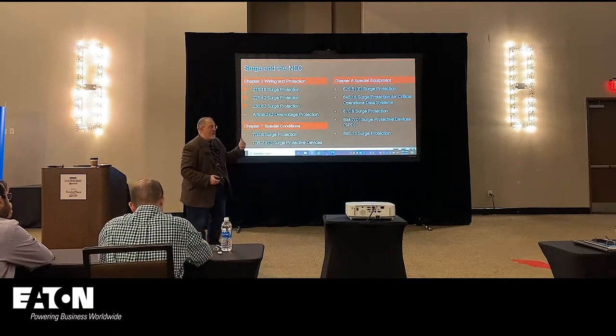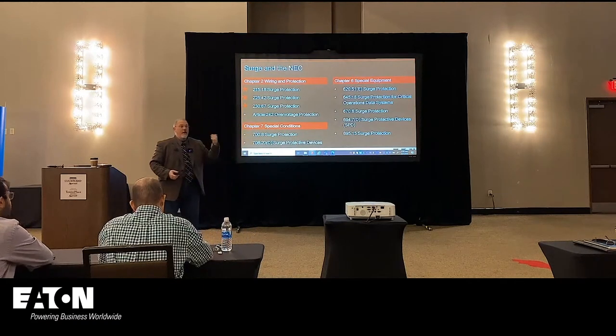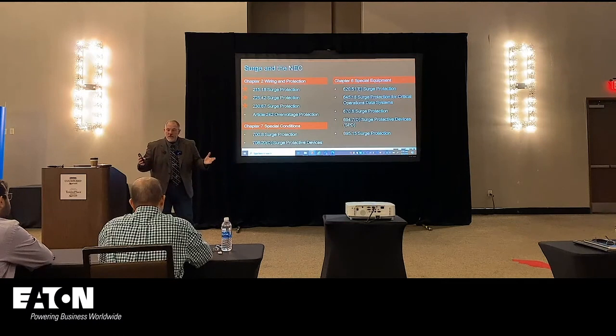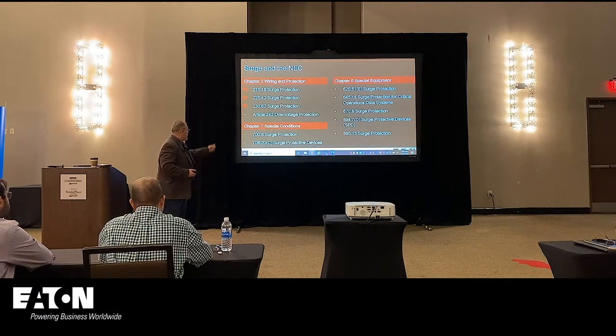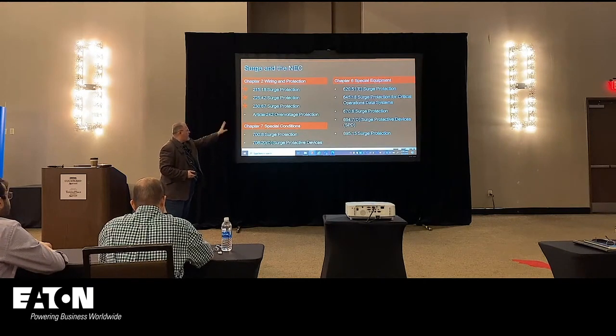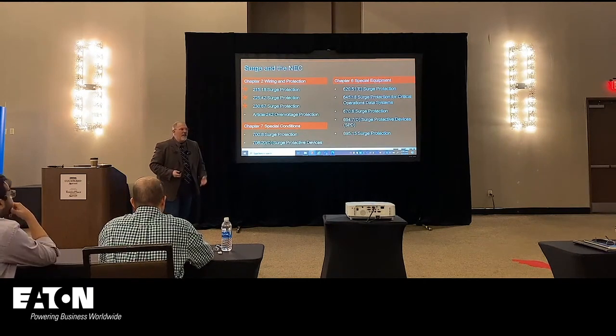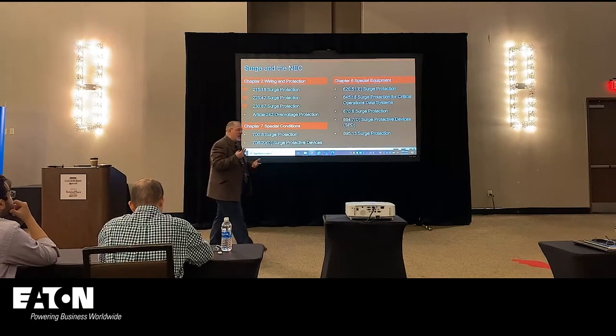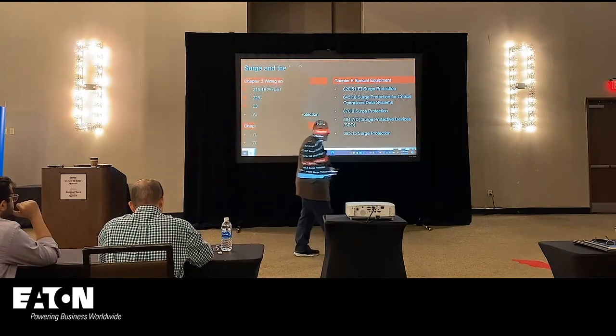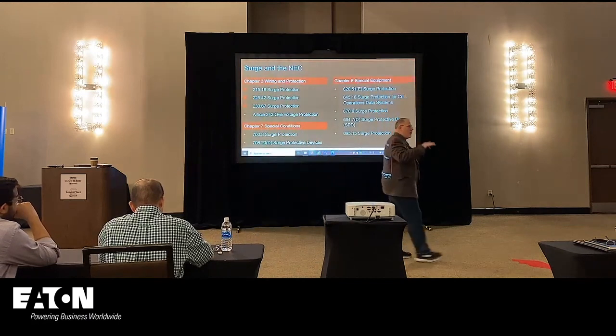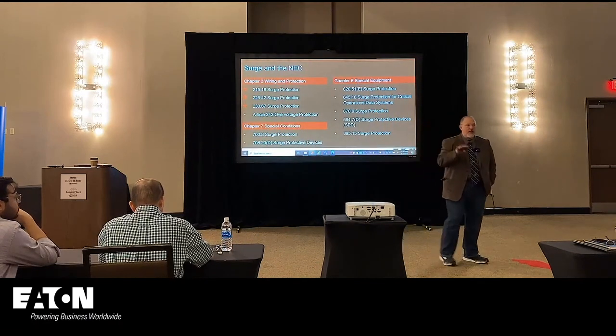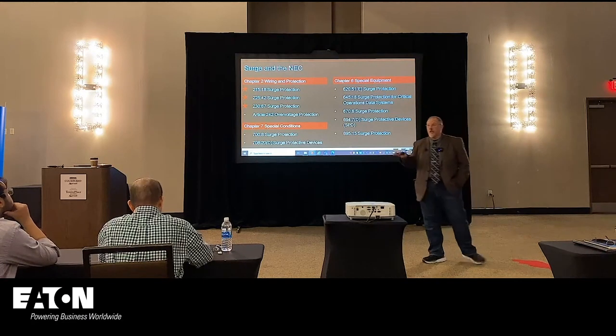And that happened because of 911. That was for your national security reasons. So Article 708 was, I would argue, the first location, and then we did 700. But then if you look at all these different special equipment, from elevator control panels and other applications, industrial control panels, you're seeing more and more surge requirements. The big change that happened last cycle was dwelling units. We put it in for dwelling unit service entrance.